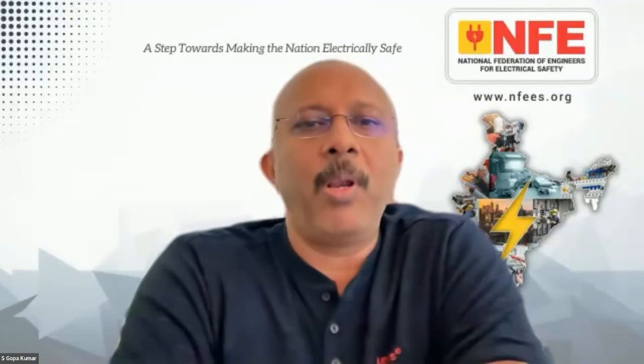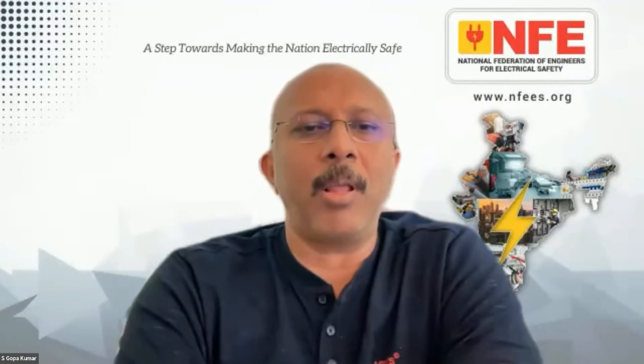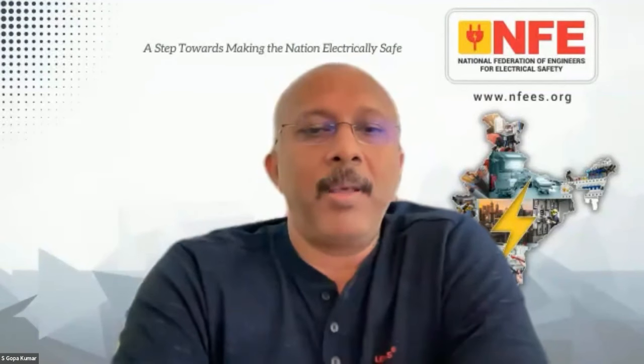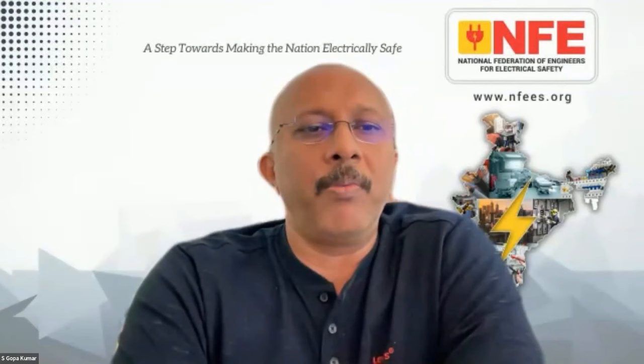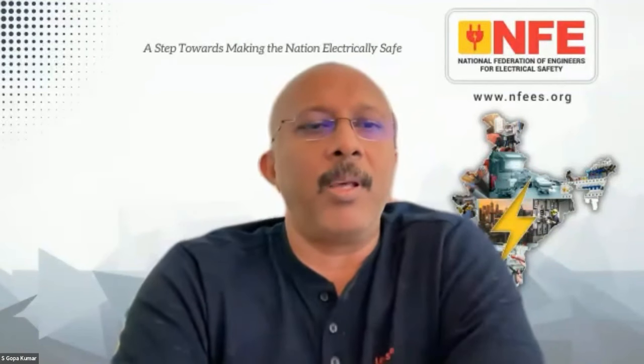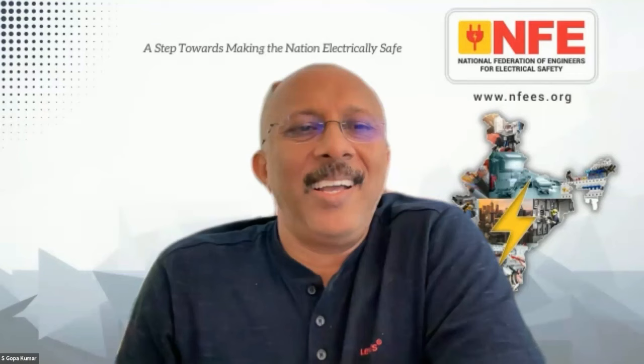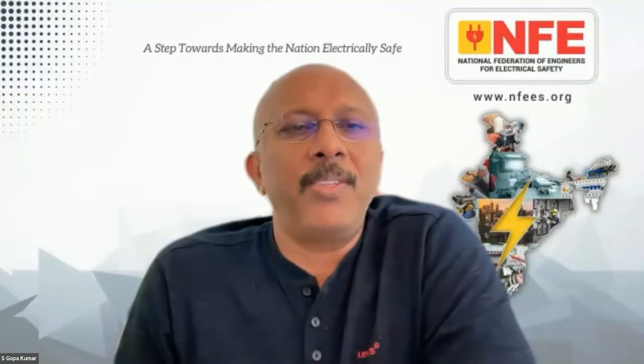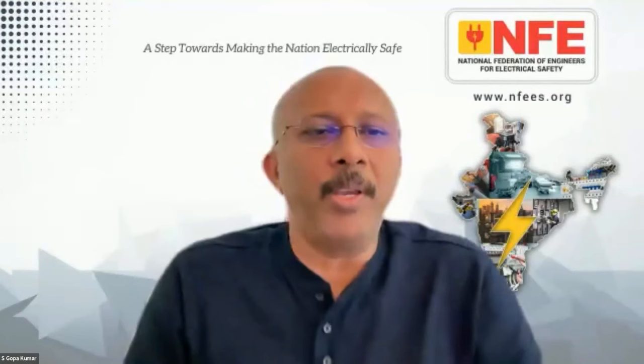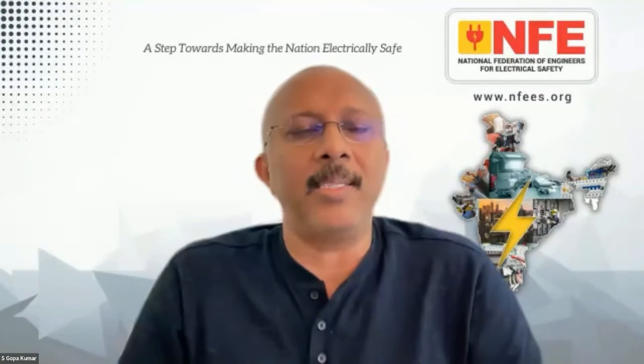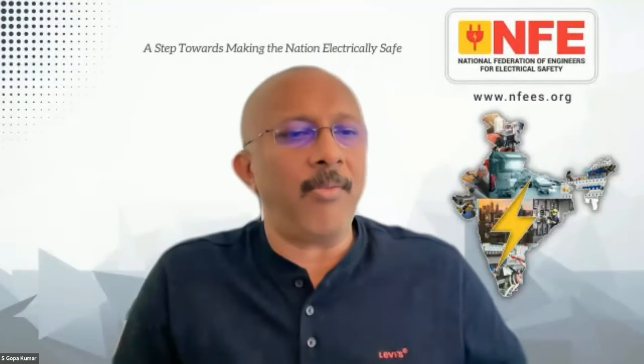Also, I agree with you, Mr. Paul, you told that the voltage-dependent RCDs are not allowed in India. I don't know from where this started, but probably in future, we will start asking the question, why is this not allowed? I think I know where from, because the electromechanical devices are very clunky and old and expensive, whereas electronics are cheaper. So a lot of the manufacturers are not making them anymore, and that's where it's come from. From my research, that is. Please feel free, if you're a manufacturer, to tell us in the comments. I could see that in one of the old versions of 7430, not the new one, the old one, it was written that voltage operated RCDs had some comments. I think probably it also started from that particular point.